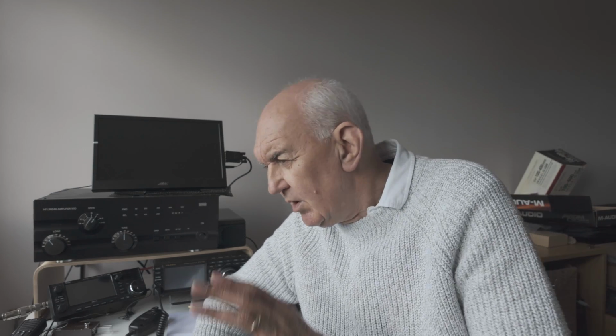So it could end up with a bit of voltage on the equipment there, because if we accept that Earth is going to be 0 volts, and that's debatable, we could find our equipment is actually at the top end of a quarter wave, and the top end of a quarter wave has got RF volts on it. So there is no way that connecting your equipment with a bit of wire down to a copper spike or a copper rod is going to be ground in terms of RF. In terms of AC voltage, totally different.